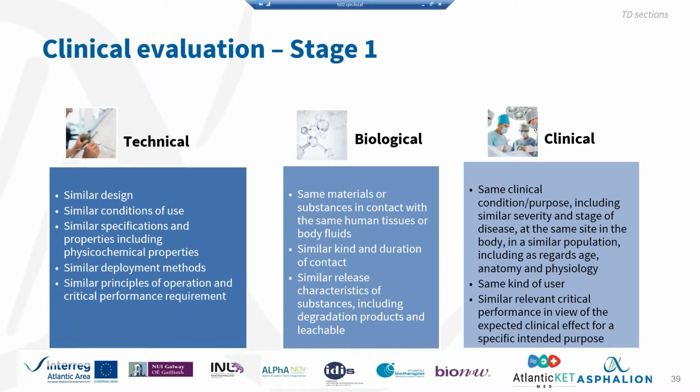It's quite complicated to demonstrate equivalence. According to regulation, it's not expected to happen really often. It's more or less expected to happen with devices of the very own manufacturer, because they're going to ask you to demonstrate equivalency, and this will not be able to be performed unless you've got an agreement with the other manufacturer. So it's quite complicated.